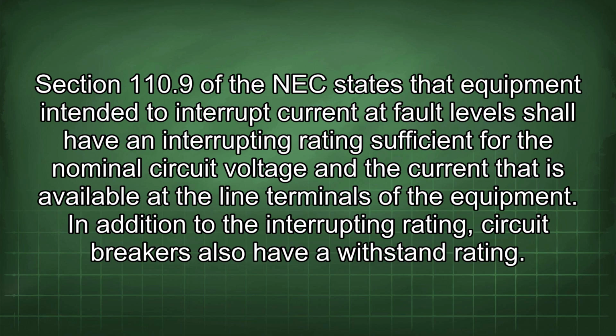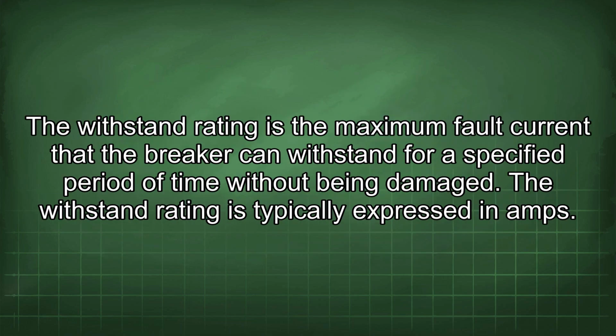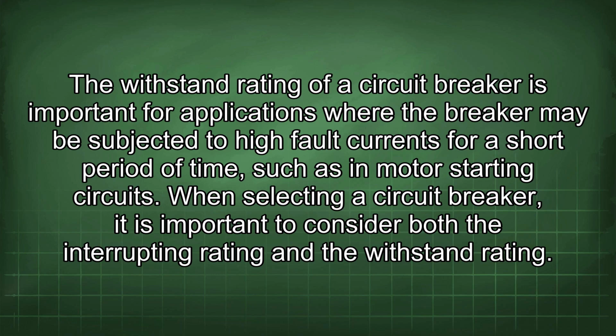In addition to the interrupting rating, circuit breakers also have a withstand rating. The withstand rating is the maximum fault current that the breaker can withstand for a specified period of time without being damaged. The withstand rating is typically expressed in amps. The withstand rating of a circuit breaker is important for applications where the breaker may be subjected to high fault currents for a short period of time, such as in motor starting circuits.